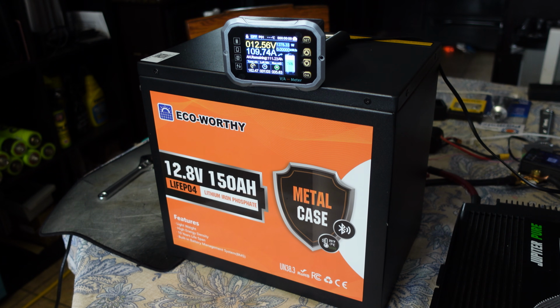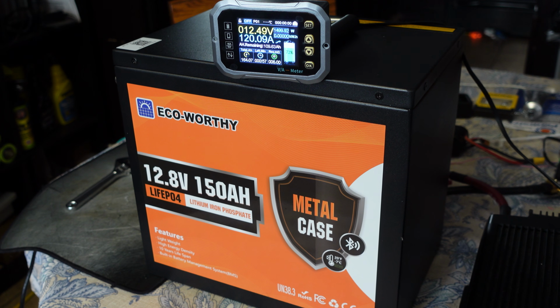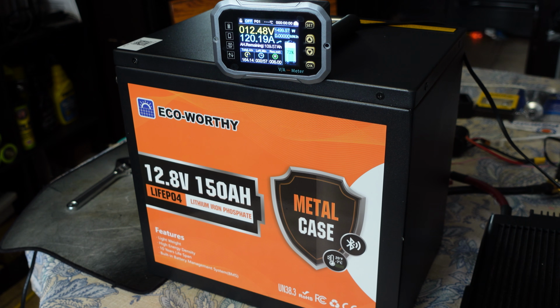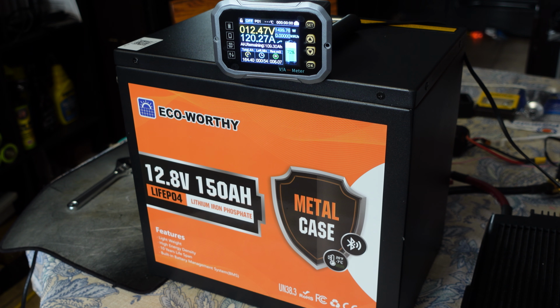So there we are, we're at 109 amps. So far so good, the battery seems to be handling it just fine. The battery's rated for 120 amps, so I'm gonna crank it up to 120. There we are, we're at 120 amps, so this is the max load that this battery is rated for. So in order to make sure it can handle it, I'm gonna let it run just for a few minutes to make sure the battery doesn't shut off.